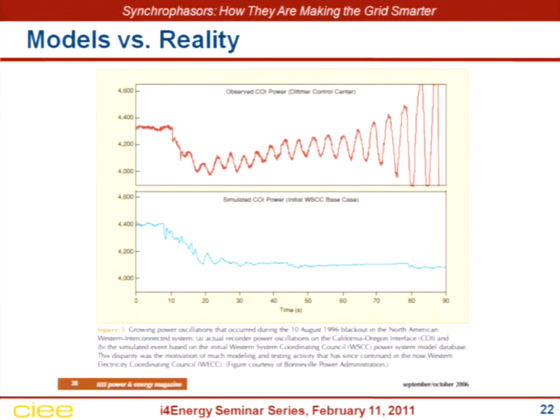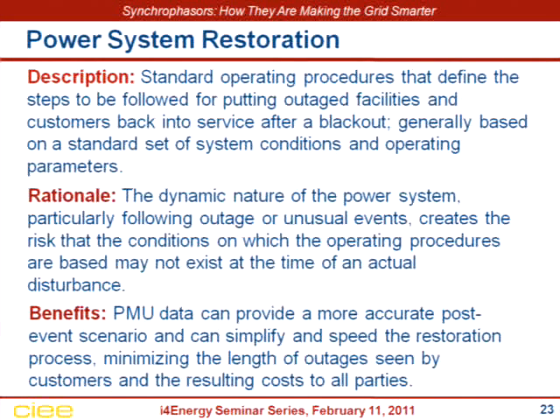After this happened, they went back, took the existing system data at the time, put it into their simulation studies, and simulated everything that went wrong. They could not reproduce this oscillation with modeling studies - the model was no good. And this model is what system operators and planners use to run the system, so they said, we've got to fix that. This is why good models are better than bad models.